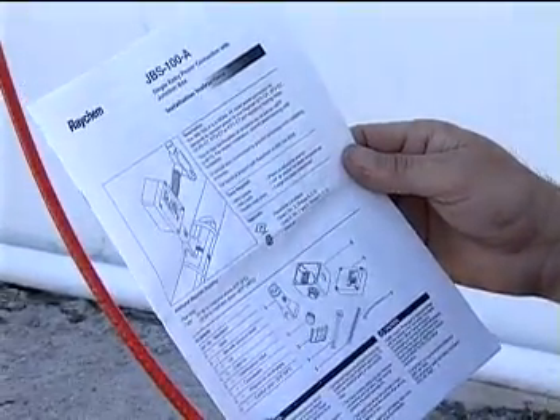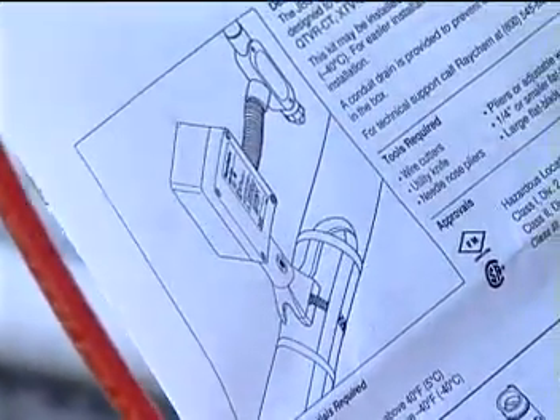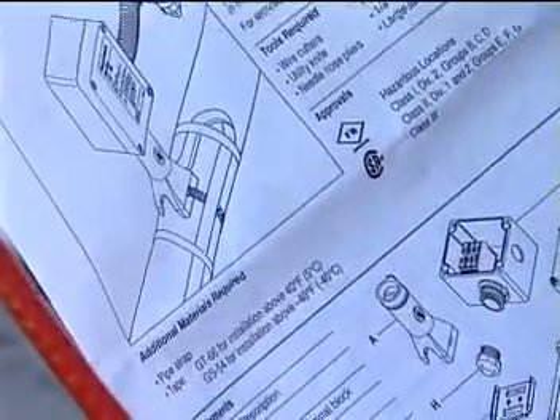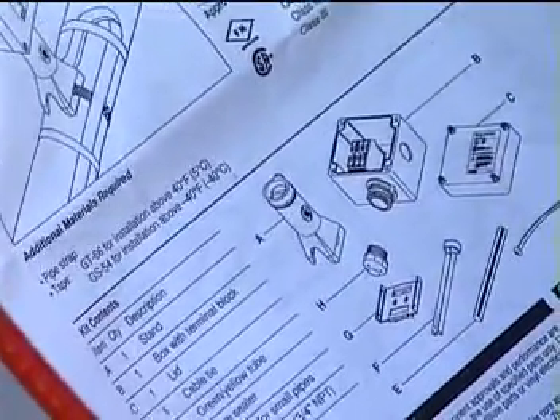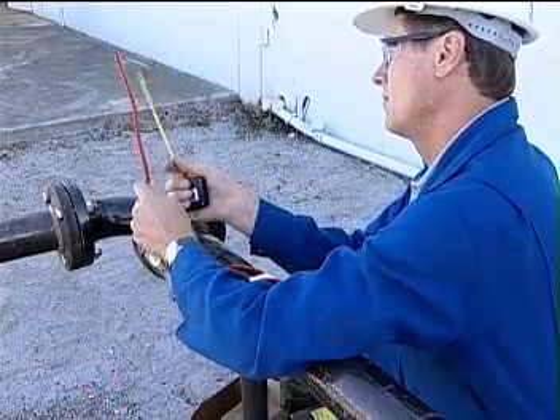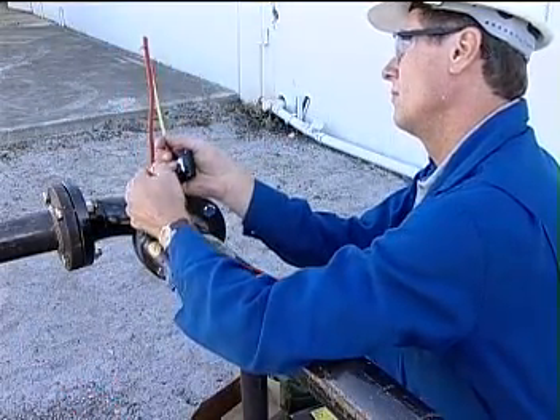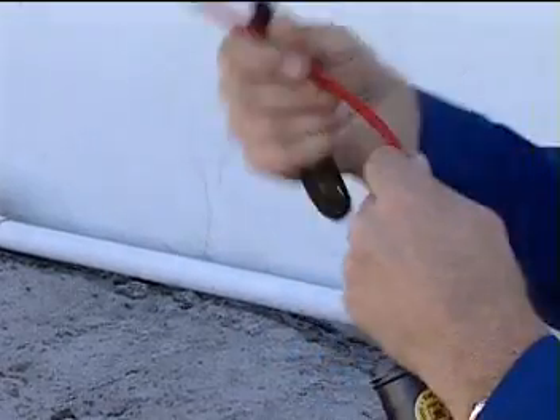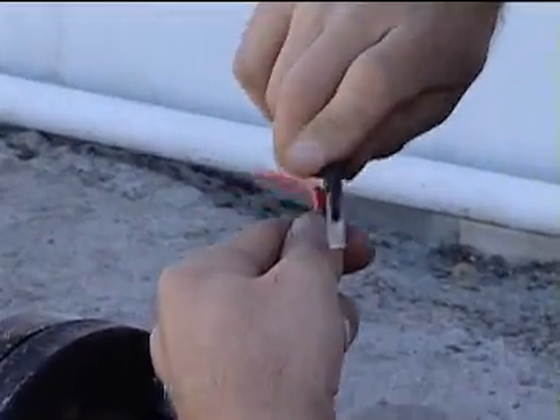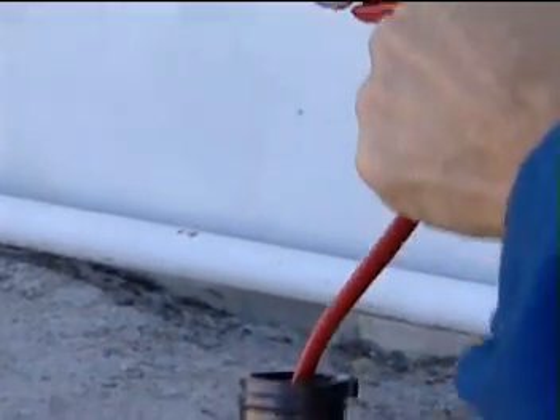When stripping Raychem self-regulating heating cables, you should be aware that conventional cable stripping techniques are not appropriate. Let's look at the correct way to strip a self-regulating heating cable to ensure proper component operation. Before stripping the cable, refer to the kit instructions for the exact length of each cut. These cuts will be different for each component that is connected to the cable.